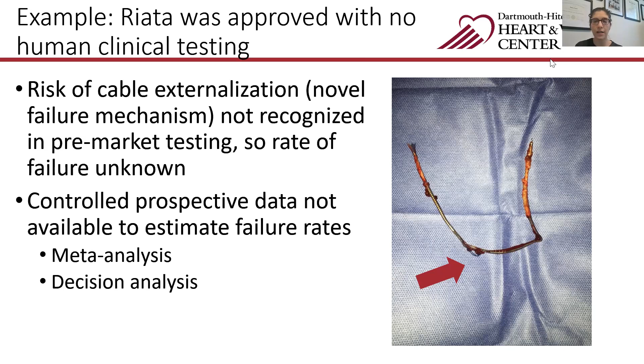This is a lot of information on this slide, but I can tell you that the rate of cable externalization reported in the literature and summarized in this meta-analysis was about 1 out of 4. So a quarter of leads that were surveilled were demonstrating this cable externalization problem, which far exceeded what was reported both by the manufacturer and what was understood to be the case by the regulators. And perhaps even more important was that the rate of electrical failure was 6%, which is far in excess of what was acceptable for an ICD lead at that time, or this time, or any other. Importantly, that electrical failure was seen with and without the presence of cable externalization.